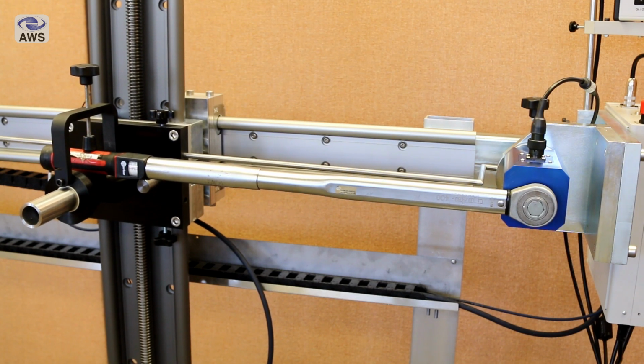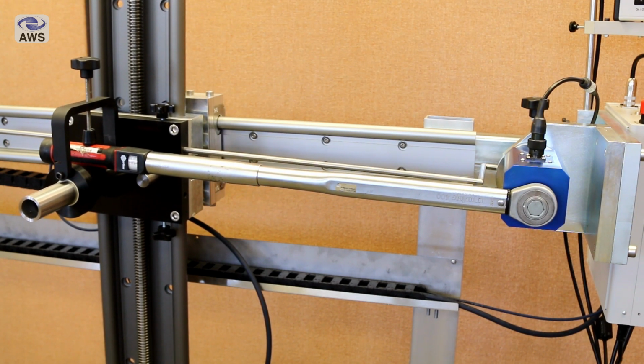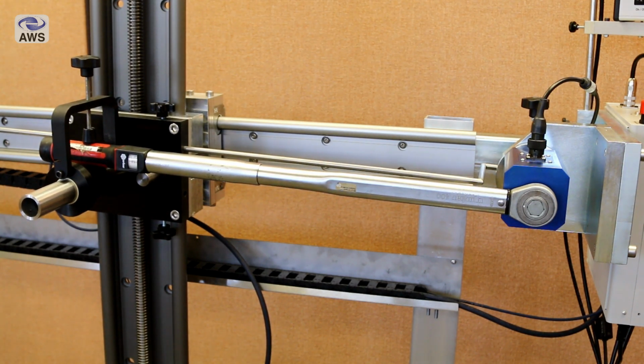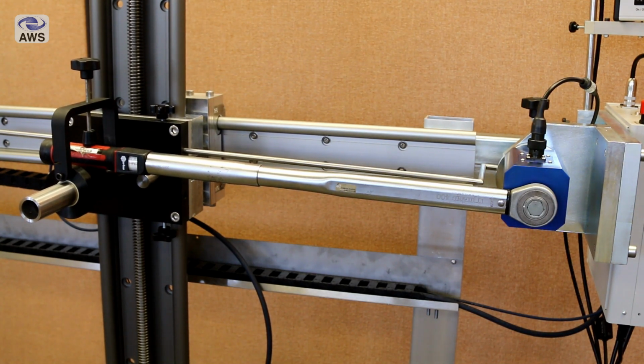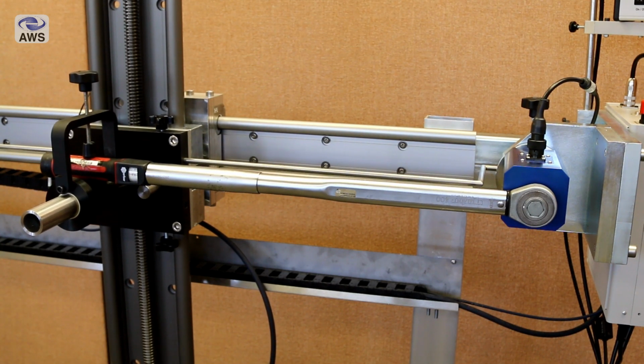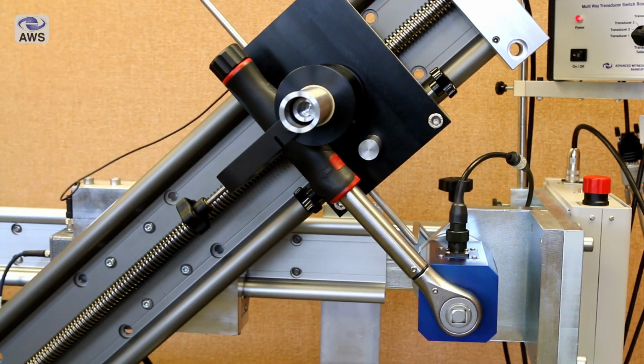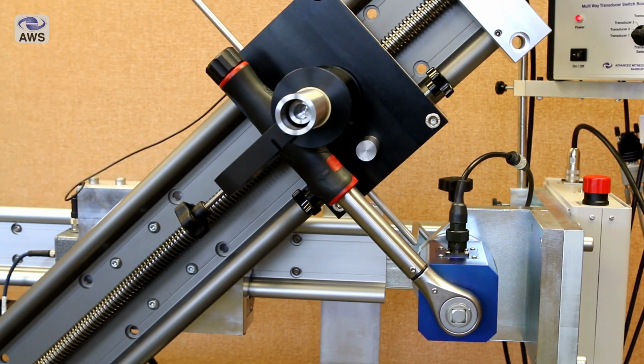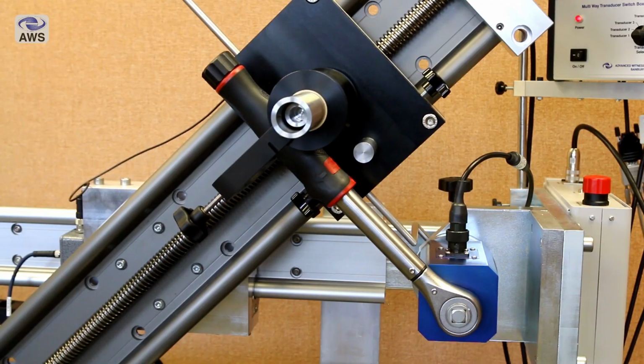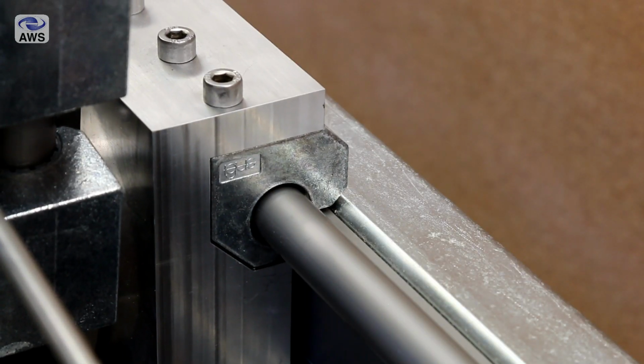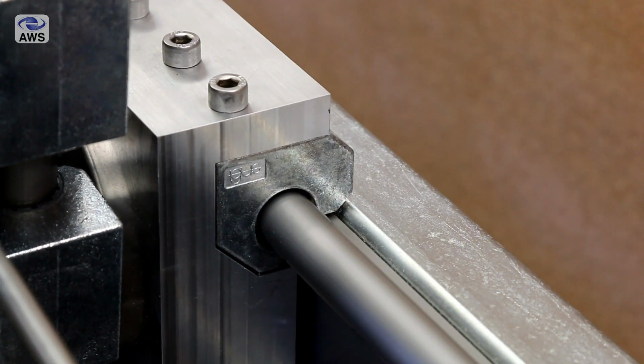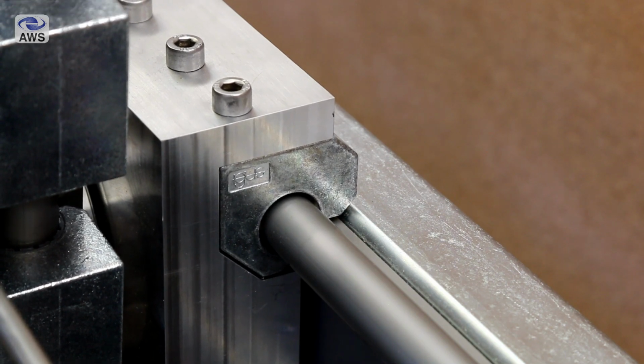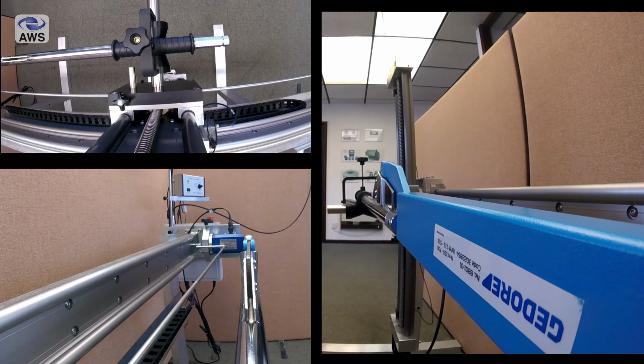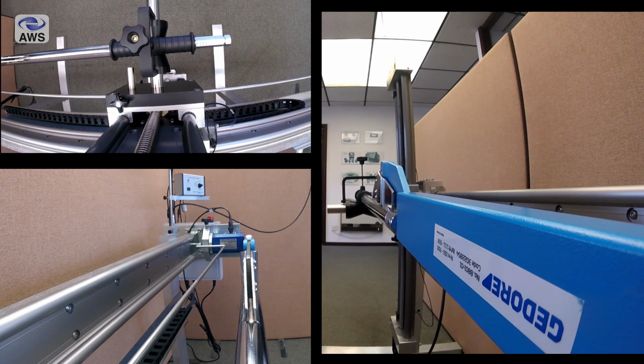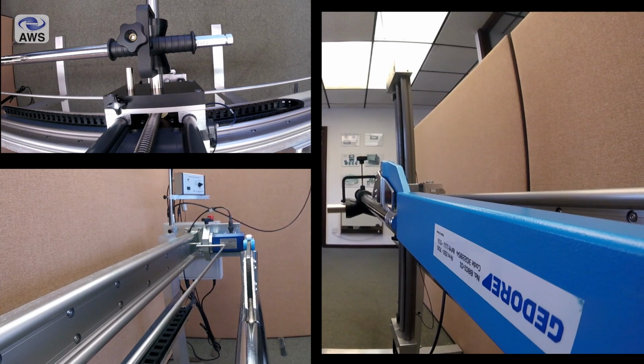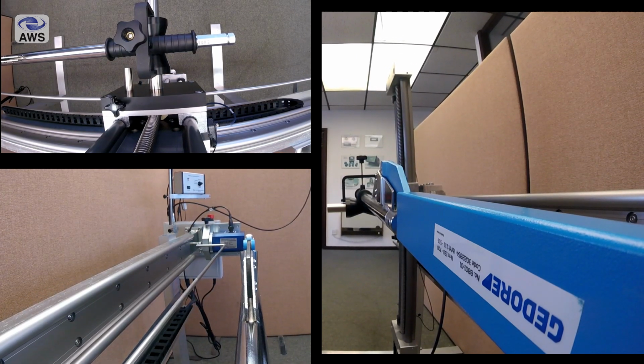The stepper motor that we have in the linear track system removes the need for operators to smoothly and consistently apply large forces on larger torque wrenches, so that makes it much easier for the operators to use. The reaction rod and linear bearings ensure the force is always applied at 90 degrees to the handle. Any losses due to friction are taken up by the stepper motor and no parasitic forces are applied to the wrench. These parasitic forces are further reduced by the vertical mounting of the torque wrench, allowing it to move freely during operation.